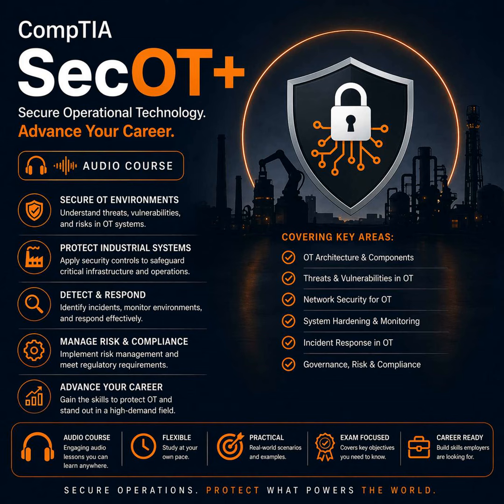Inherited risk is often easiest to see through the lens of technical debt, which is a concept that translates well into OT. Technical debt is the accumulation of design and maintenance shortcuts that were taken for good reasons at the time, like speed and cost, but that create long-term fragility. In OT, technical debt might include undocumented connectivity, shared accounts, unstandardized configurations, and patch backlogs created by constrained maintenance windows. It might also include inconsistent segmentation, where some zones are well separated and others are not, making the environment uneven and unpredictable.